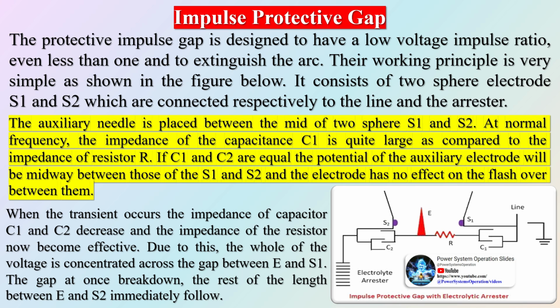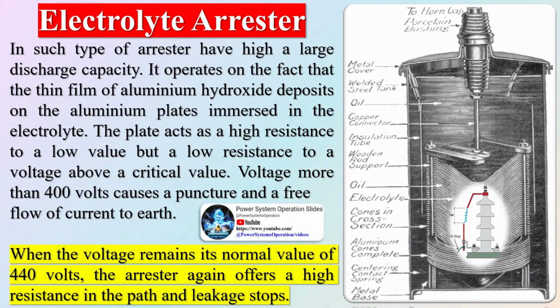as soon as the transient voltage has fallen below the breakdown value. There are many types of lightning arrestor which are used to protect the power system. The choice of the lightning arrestor depends on factors like voltage and frequency of the line, cost, weather condition, and reliability. Characteristics of an ideal lightning arrestor. An ideal lightning arrestor should possess the following characteristics: no current draw in normal conditions. It should not draw any current during normal operating conditions, meaning its sparkover voltage must exceed the normal or abnormal power frequencies that may occur in the system.